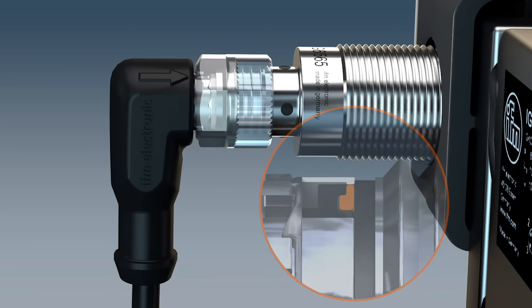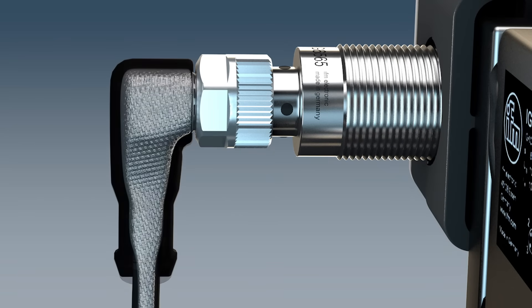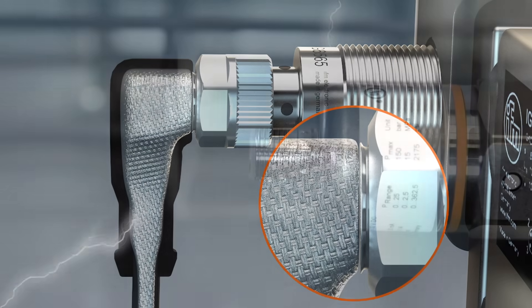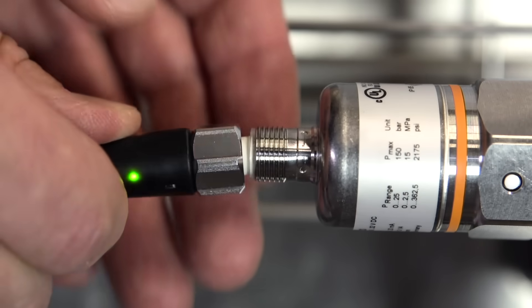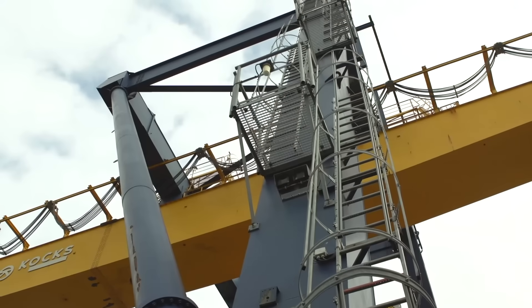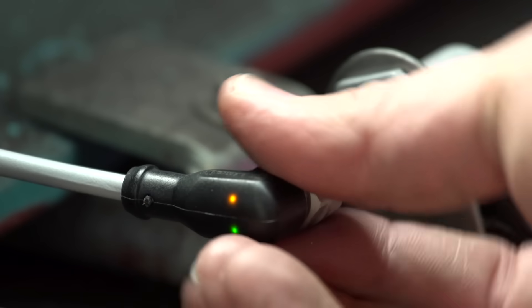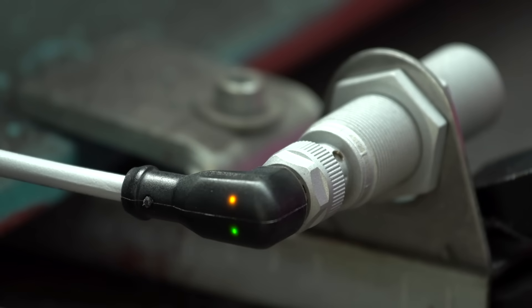The very low ohmic contact resistance between the connector nut and the sensor housing ensures efficient screening and trouble-free operation. An asymmetrically acting vibration protection allows installation even at locations which are difficult to access. Ecolink connectors can be tightened and loosened manually.